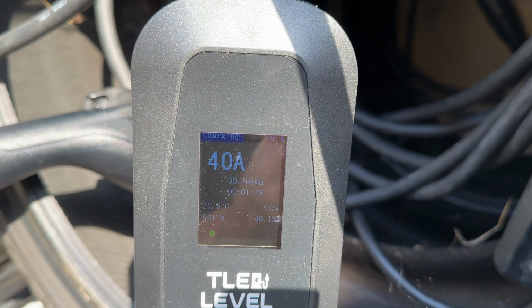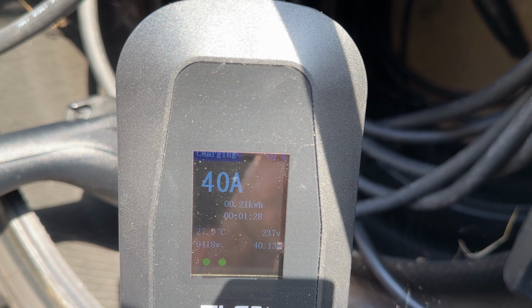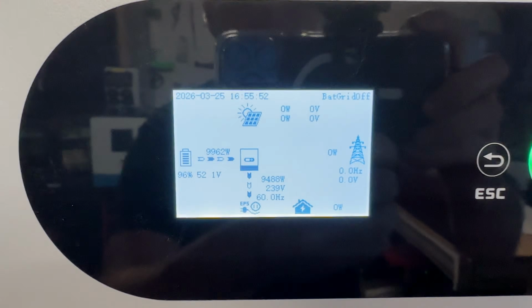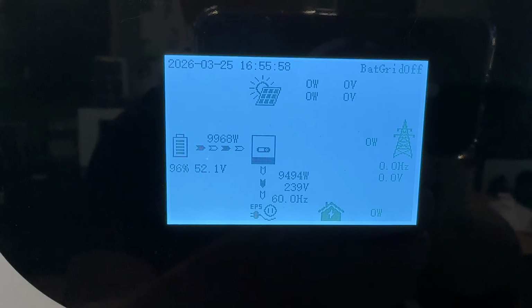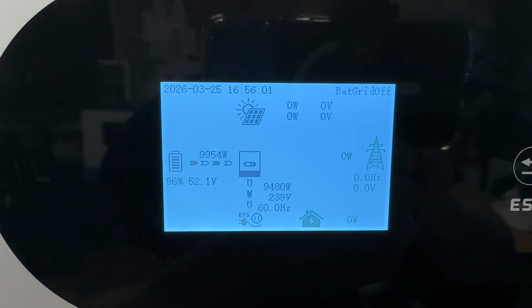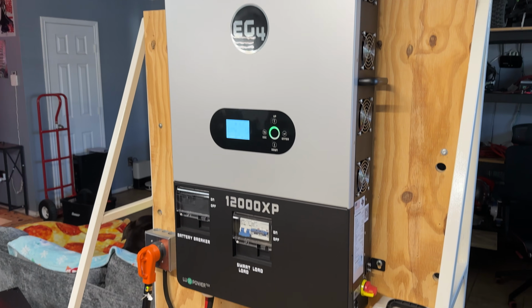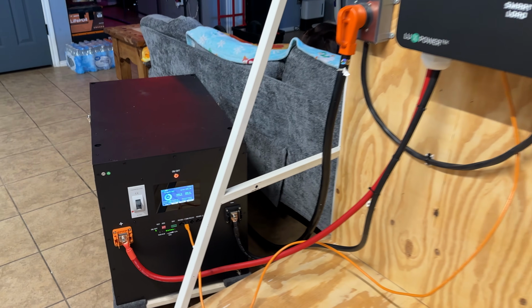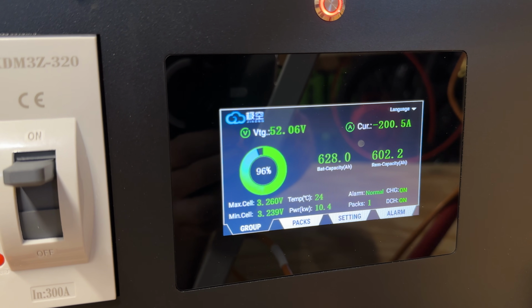As you guys can see by the charger, we're putting in 40 amps, or about 9,400 watts, and the inverter's handling it just fine. The fans are running. It's almost 10,000 watts on the DC side, about 9,500 on the output side. This inverter's handling it like a champ. Let's see how many amps we're pulling on the battery. We're right at 200 amps.